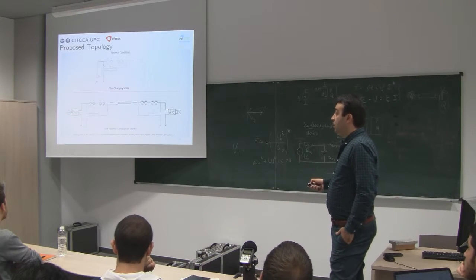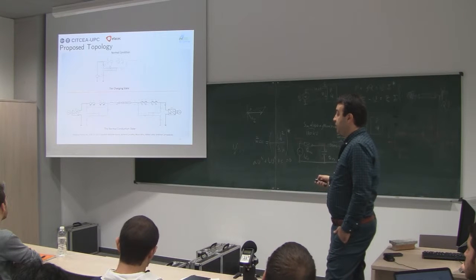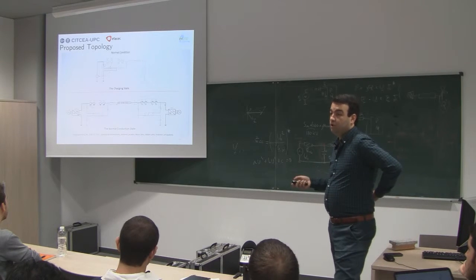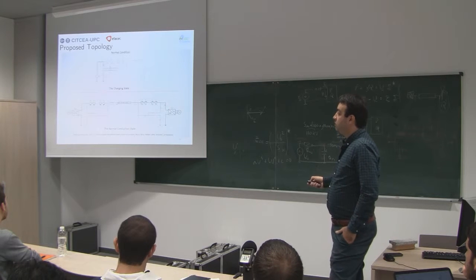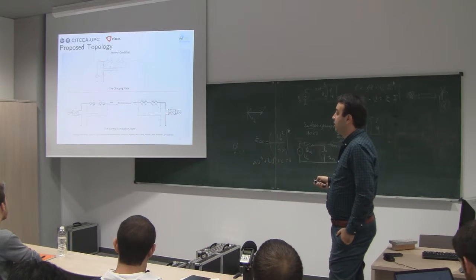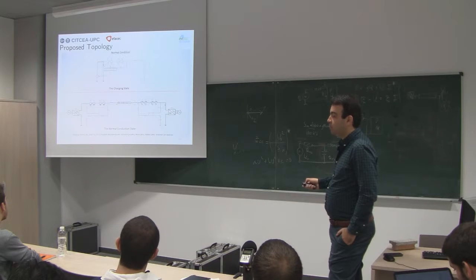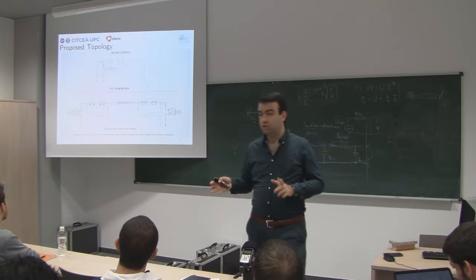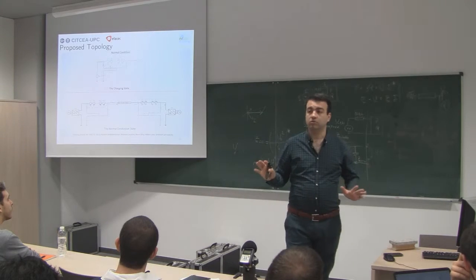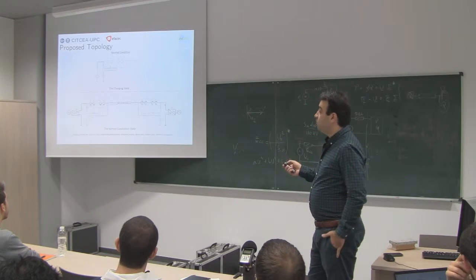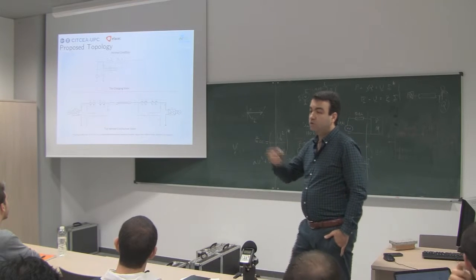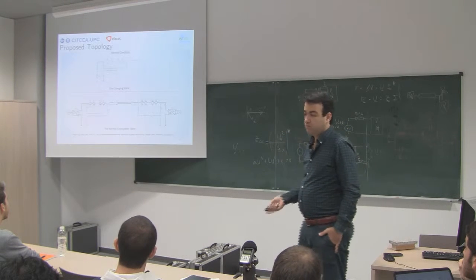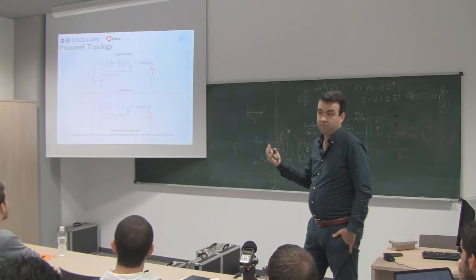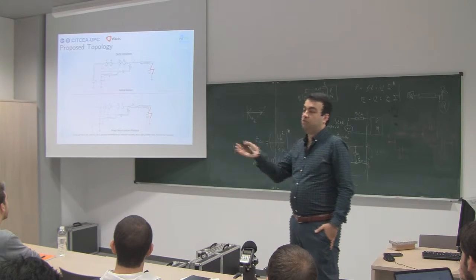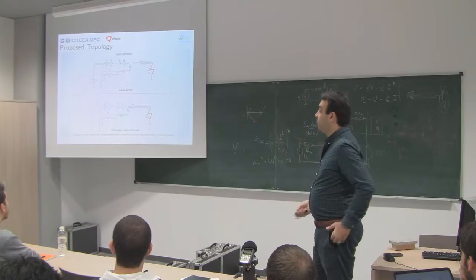So you can see that the bidirectional current flow is maintained, no problem. And you can change the current flow again. I mean, the current can flow through these IGBTs and this cable and these anti-parallel diodes. So the bidirectional current flow problem is also solved here, but with the use of half of the IGBTs. Half of the IGBTs means half the power losses and maybe half the investment cost in terms of implementing that branch.